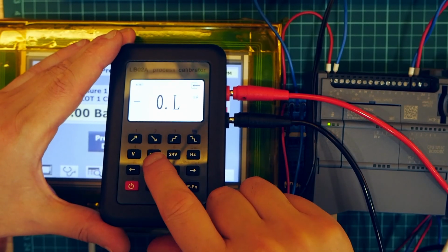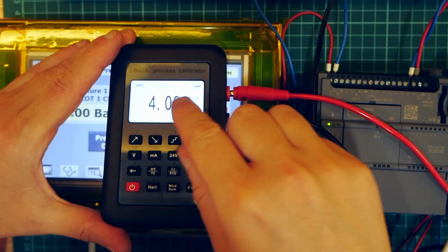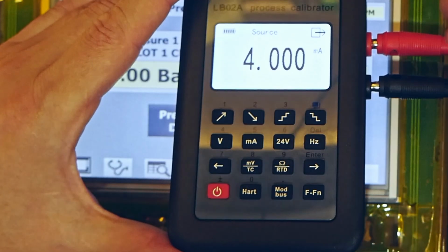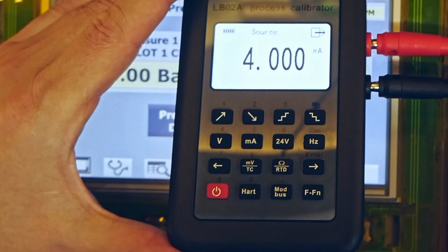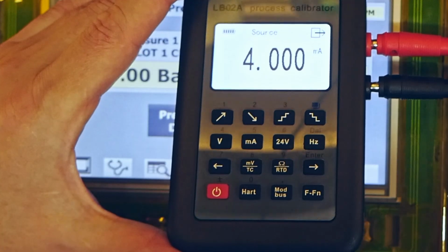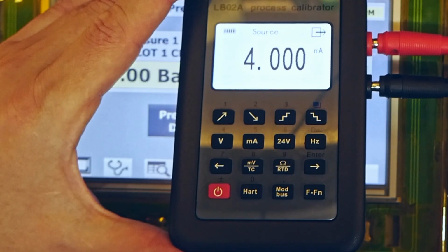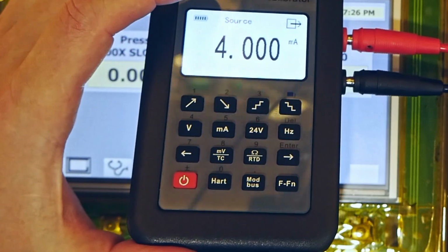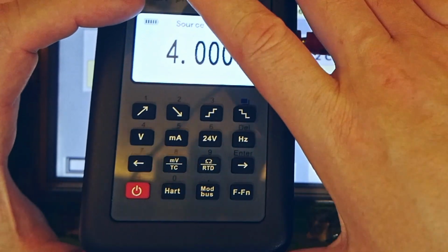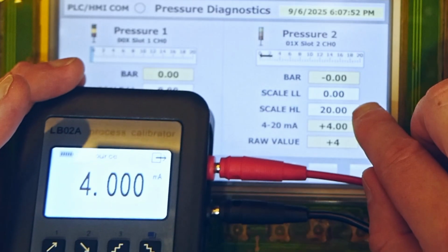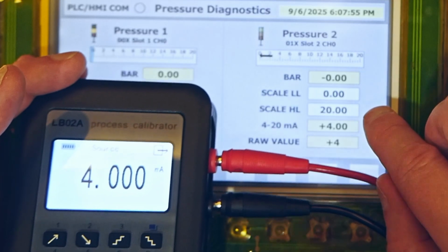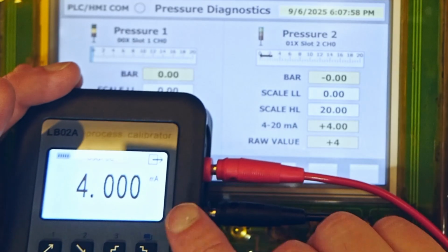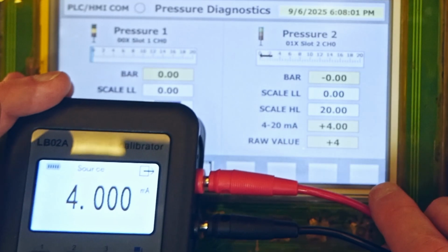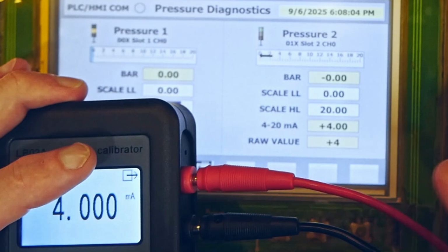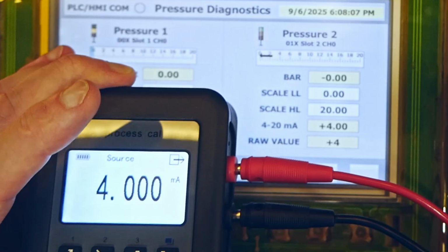So again, if we press the milliampere push button again, we are right now in sourcing mode. So we are outputting around 24 volts, and we can set what kind of current we are outputting. Okay, so I connected these wires to my analog input card. Means we have 4 milliamperes, that means we have 0 bar pressure. If we have 20 milliamperes, we will have 20 bar pressure. So again, same situation as with voltage.